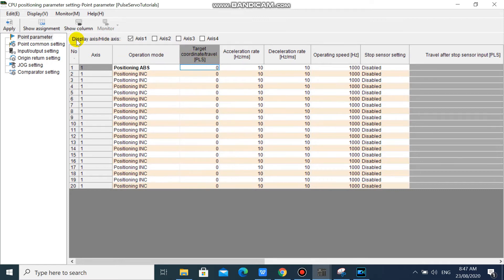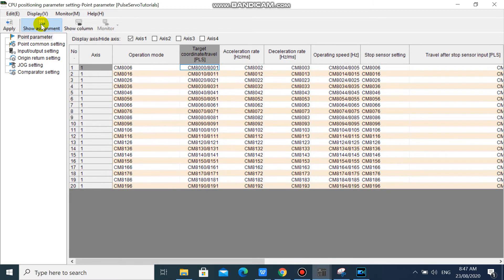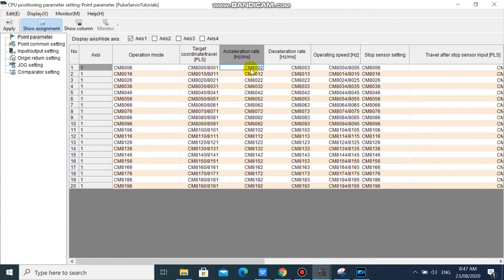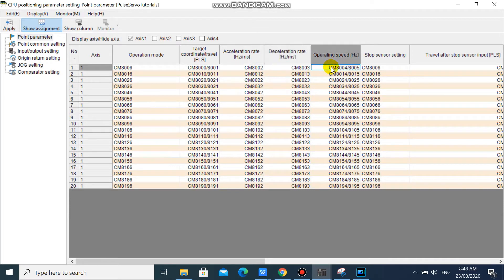You can click Show Assignments so that you can see assigned devices. Your servo target position is from CM8000 to CM8001, double word. Your acceleration rate is CM8002, single word. Your deceleration rate is CM8003, single word. And your servo speed is CM8004 to CM8005, double word.